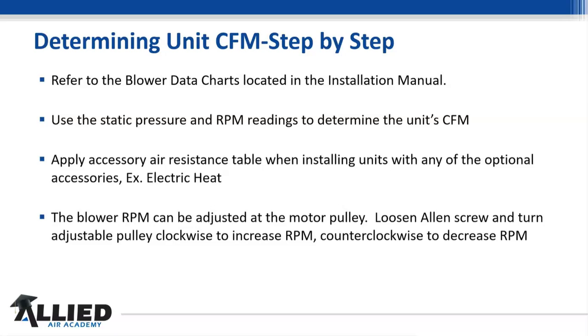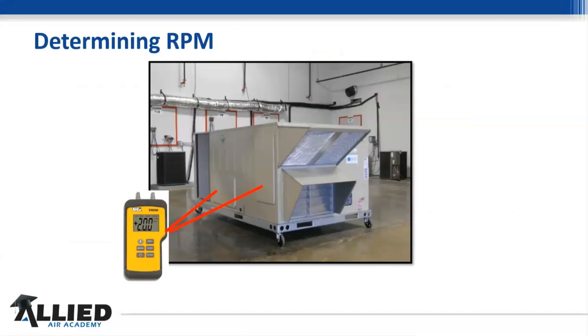I got some really good illustrations. But one of the things, when we do these hands-on classes with this, I had a 10-ton unit, and on that unit, we could take our static pressure right on these doors on the outside. You got to be careful, if you got an economizer in here, to make sure to get on the opposite side of the economizer, in other words, the downhill flow of the air. So you want to make sure you don't run across the economizer. You want to go to the backside, and you can get the readings here, which makes it real simple.